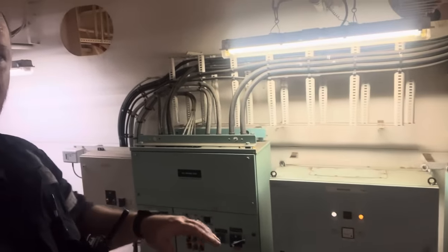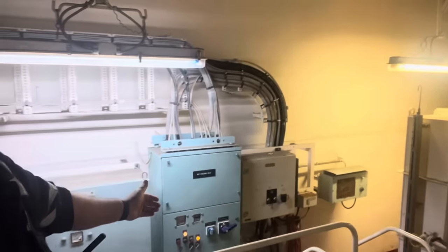There are multiple redundancies in the way the cabling is run. This cabling on the port side runs up the port side of the ship, while the cabling for the other motor — fed off the main switchboard — runs up the starboard side. The reason you do that is if you're ever in a collision and the cables are severed, you have an alternate supply. Here we see the number one steering motor control on the opposite side of the ship. The control cables from the bridge run down opposite sides so that if there's a fire on one side, you still have the other side.